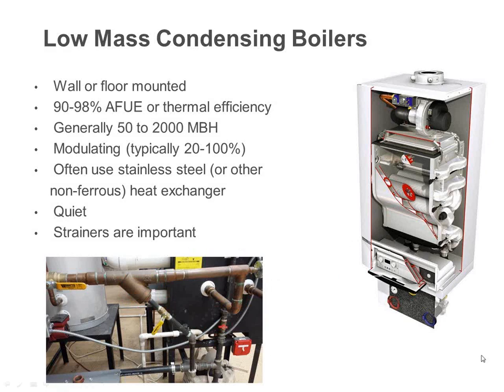Okay. Most boilers do have built-in sequencers for multiple boilers. All of them, like I said, should have outdoor air reset. Without it, you're basically cheating your customer. A lot of them will stage or do lead lag. And almost all these boilers have domestic hot water priority. It's just so simple to do off these high-efficiency units. Now you've got a high-efficiency domestic hot water heating system.